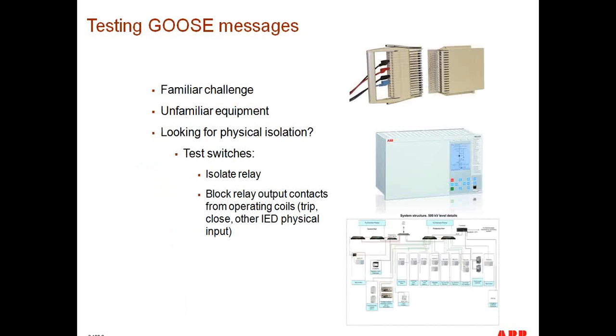And that takes us to the final topic of our presentation today, which is testing GOOSE messages. Testing for end users today is a familiar challenge. The testing itself is quite familiar, but how to test in a GOOSE message-based system, now you have unfamiliar equipment and unfamiliar technology. And one of the questions that I often receive is, where is the physical isolation? Where is the physical barrier? Since GOOSE message is not something that's tangible from a field engineering perspective. There's no way you can break that connection other than pulling the network cables out. And even then, there's really no direct feedback that you can use to determine the value of the variables being sent by that particular device upon reconnection to the network.